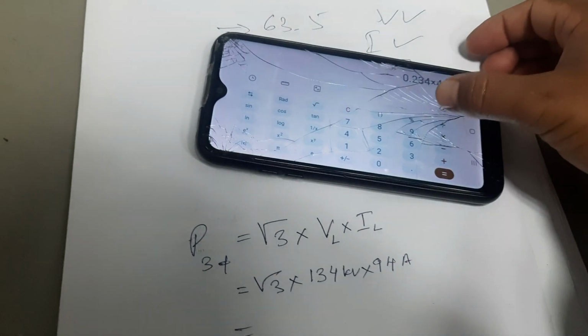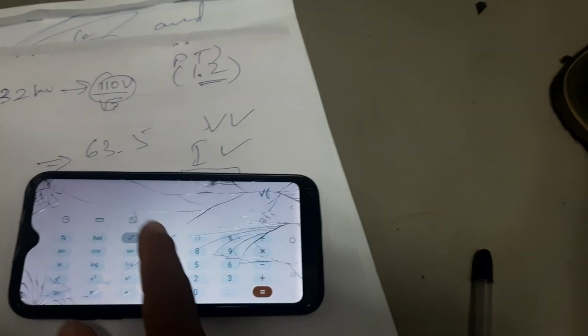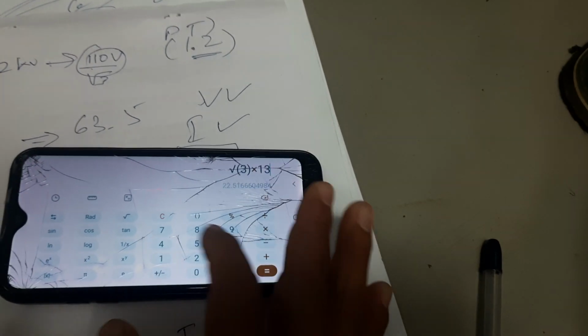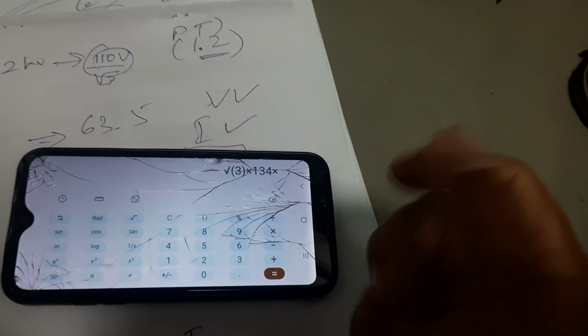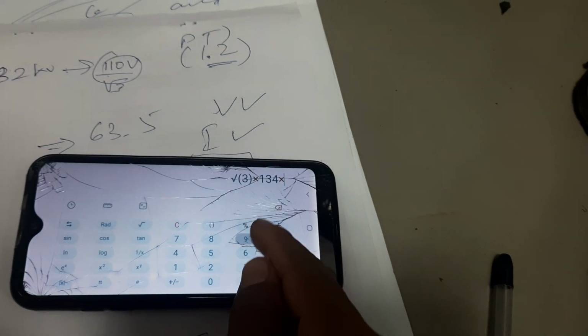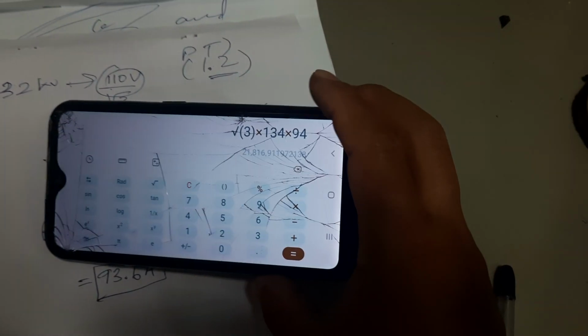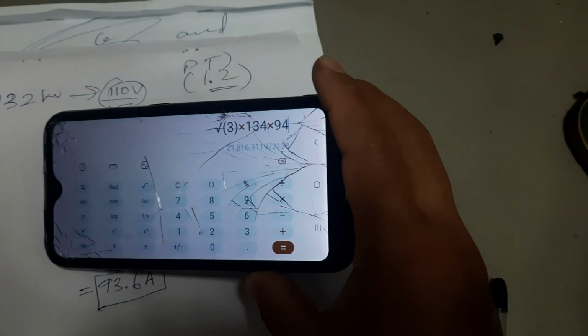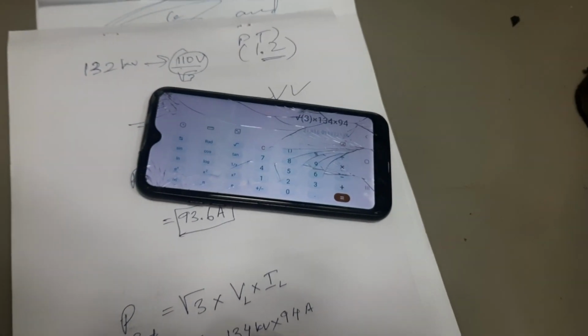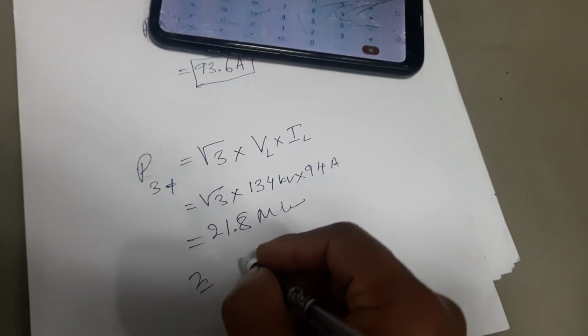So let us do the calculation again. For this, 134, let me write 134 root 3 also, no problem, I can write like this. And then where is the closing bracket? Okay, root 3 closing bracket into bus voltage of 134 into the current, which is the value that I have taken from the BCU, 94. Okay, and you are getting 21,816, but if I have to express it in terms of megawatt, it will be 21.8 megawatt, or roughly you can say 21 megawatt, or roughly you can say 22 megawatt.